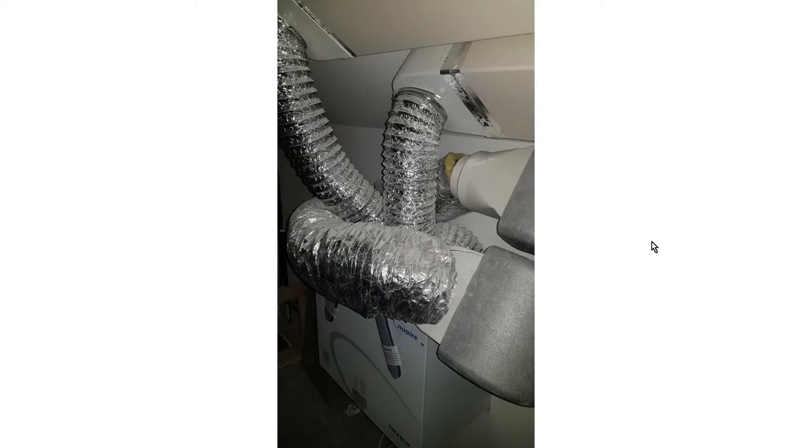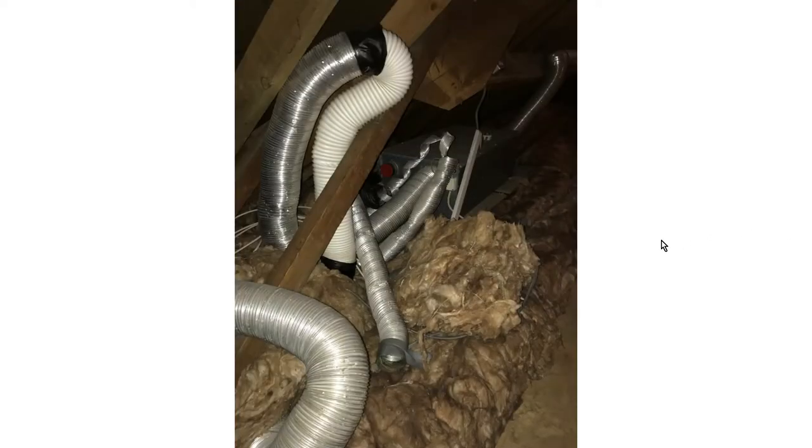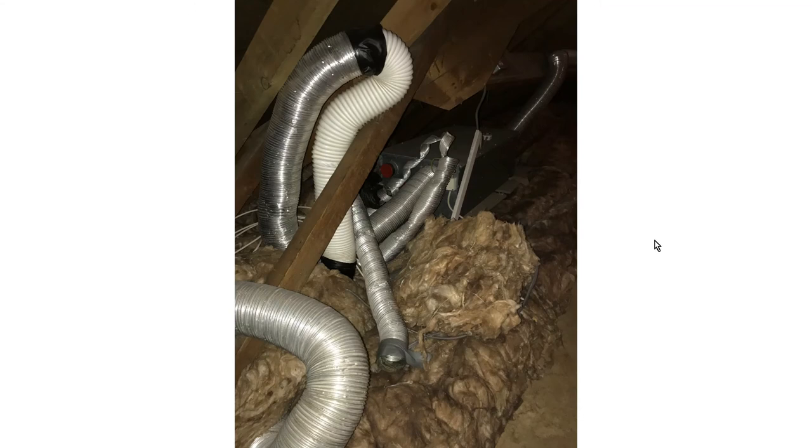This one is a big pile of bits somebody bought online. It's been installed by an inexperienced installer who was following a free design. It's held together with tape there's no insulation where it needs to be so there's going to be condensation problems and you can't get the front of the machine off to service it so it's a problem waiting to happen. This is a problem that has happened. The less said about this the better. It's totally ineffective there's no heat recovery and all it's doing is sucking airborne mineral wool particles up here and distributing them around the home which isn't ideal.